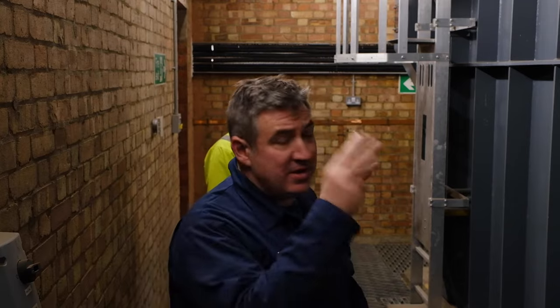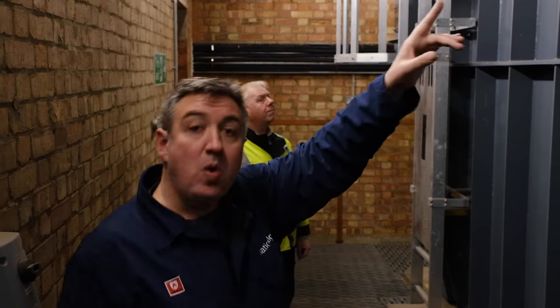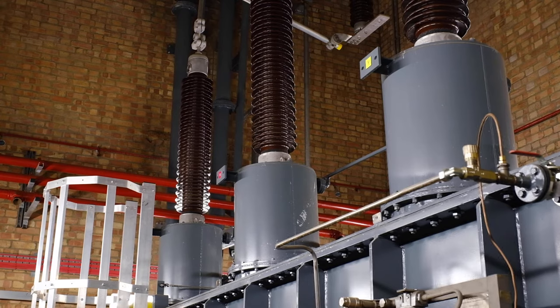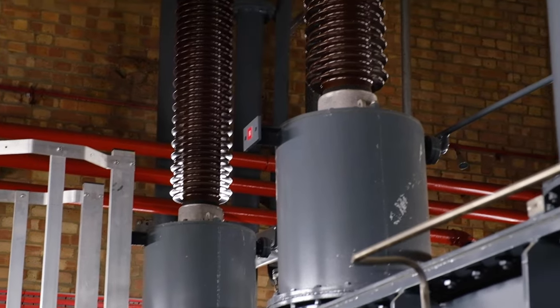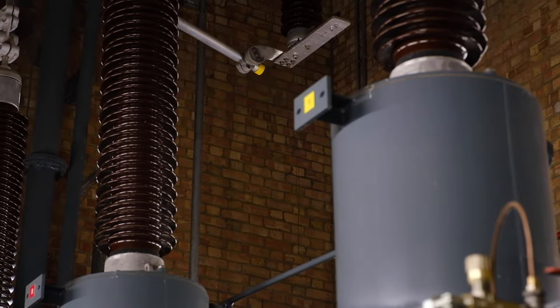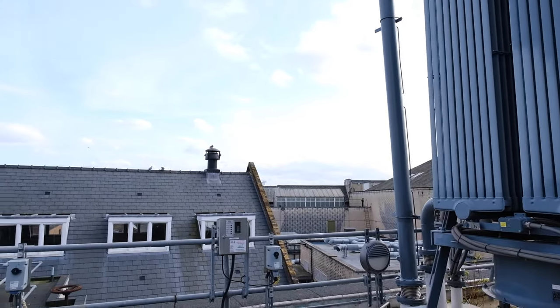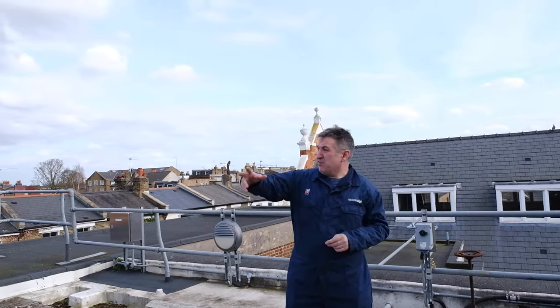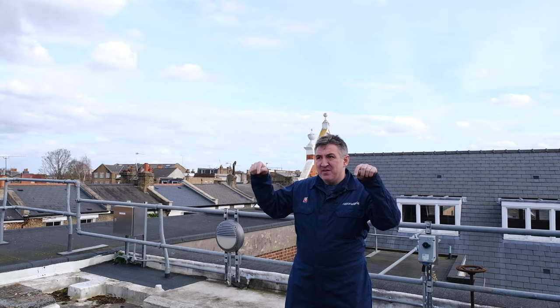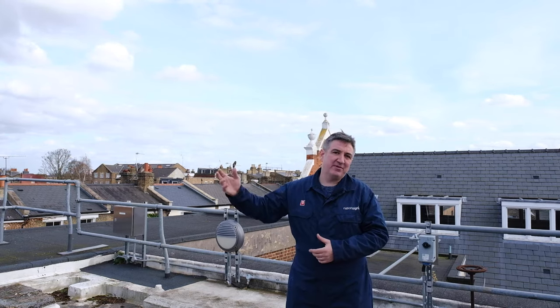Throughout the whole of London, the phases are rolled. So from left to right across the transformer we connect blue, red, yellow instead of red, yellow, blue. That's known as the Battersea colours, because someone in the 1920s at Battersea power station got the phases crossed, and that set the standard — everything done from that day to this has to integrate with what's already there. It's remarkable: we're in the very heart of Stoke Newington, Church Street just over there, the Town Hall, Clissold Park, surrounded by dense urban development, and this relatively small site supplies the energy to over 50,000 homes.